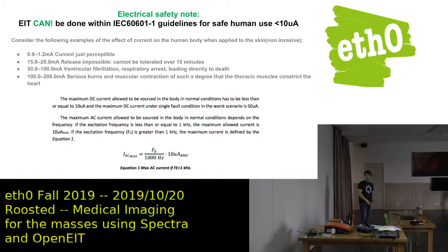The allowed current also goes up with a specific formula as stated in the IEC regulations. The problem with having very low currents is that you don't get a lot of voltage for a specific impedance. So you need very advanced electronics, good ADCs, low noise measurement setups, and expensive chips to actually produce results out of these small currents. But that's the only way you can do it legally and safely.